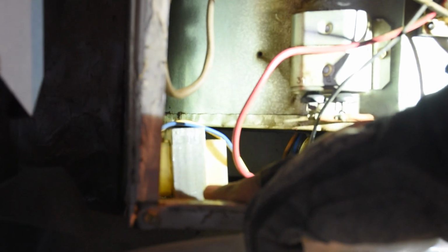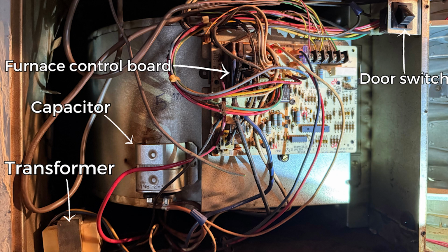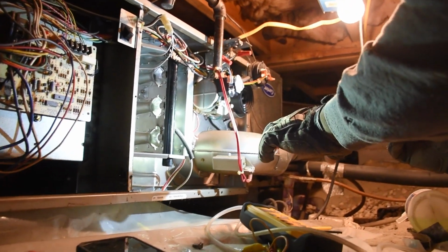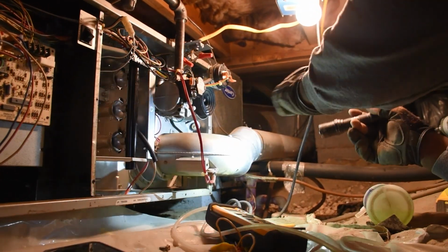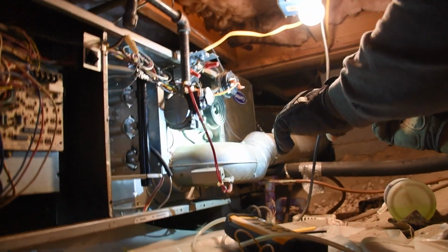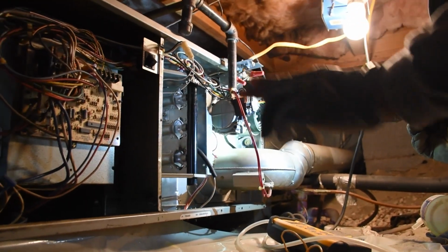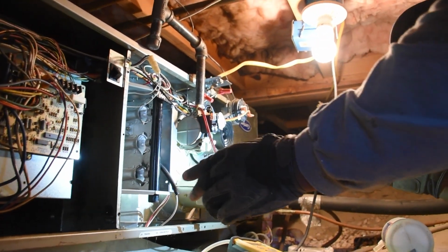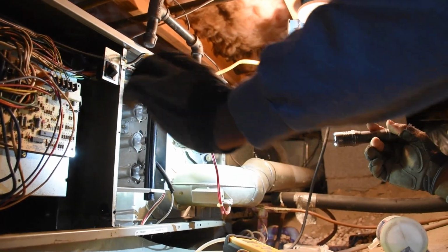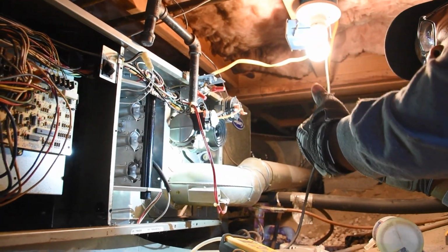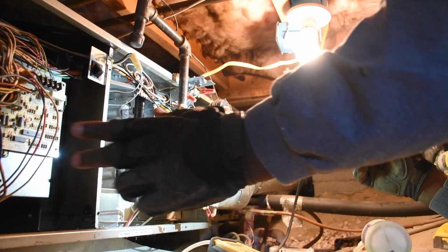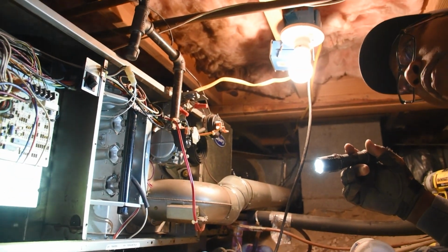It reduces the 240 volts down to 24 volts, which ultimately operates all the lower voltage components inside this. All the safeties, gas valve, pressure switch, low voltage is what passes through all of these. So when one of these gets triggered, it triggers and shuts the system off, which ultimately shuts off the thermostat, because the thermostat operates from low voltage also, not high voltage.